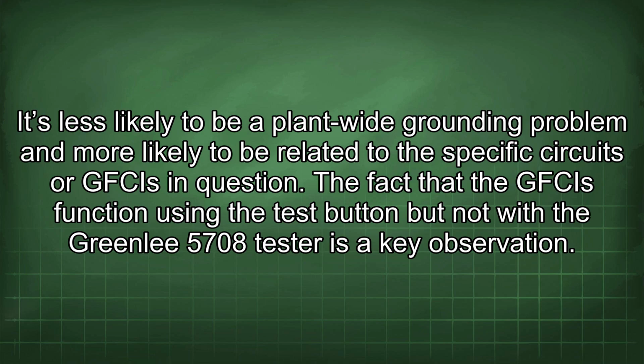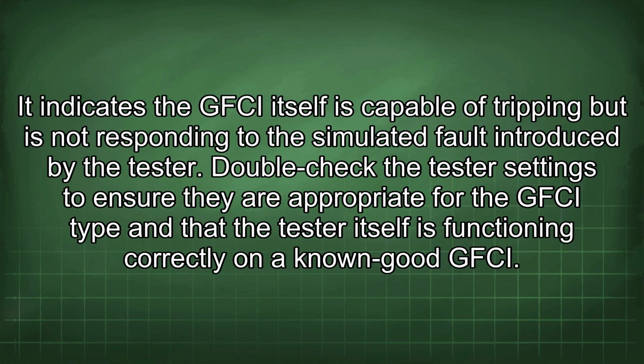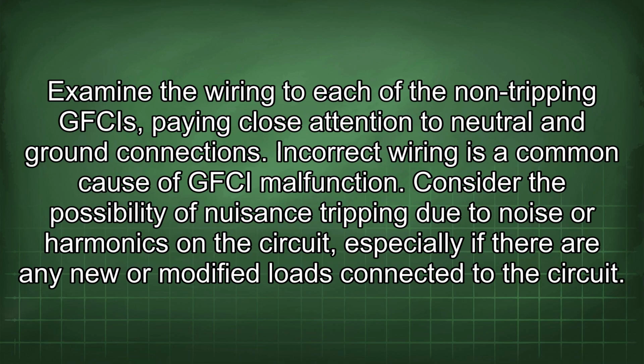5708 tester is a key observation. It indicates the GFCI itself is capable of tripping but is not responding to the simulated faults introduced by the tester. Double-check the tester settings to ensure they are appropriate for the GFCI type and that the tester itself is functioning correctly on the known good GFCI. Examine the wiring to each of the non-tripping GFCIs, paying close attention to neutral and ground connections. Incorrect wiring is a common cause of GFCI malfunction.